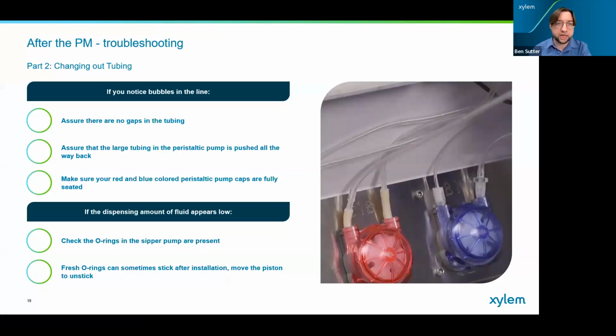When you do eventually reattach these in the next step, you want to make sure they're on all the way. You want to assure that the large tubing in the peristaltic pump is pushed all the way back. When you saw Jason push those down in the back, down at the bottom, the big part of the tubing, the part that's pictured here, you want to make sure that's all the way back under that white wheel. The more snug it is back there, the better. And you also want to make sure that those caps are fully seated that go on top of them. If they're not, then it could affect how much fluid goes through there, and that could affect performance. So we want to make sure those do click as he indicated.